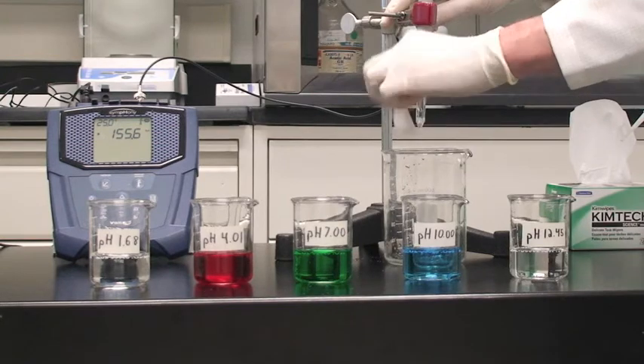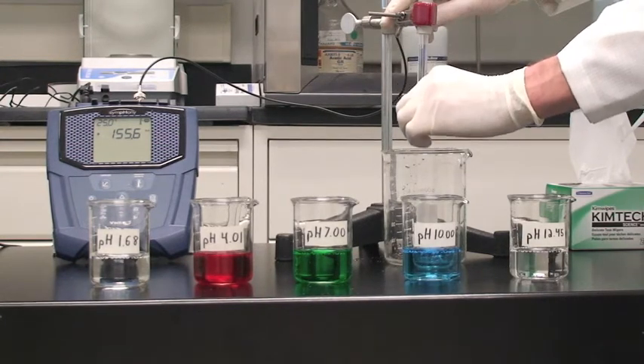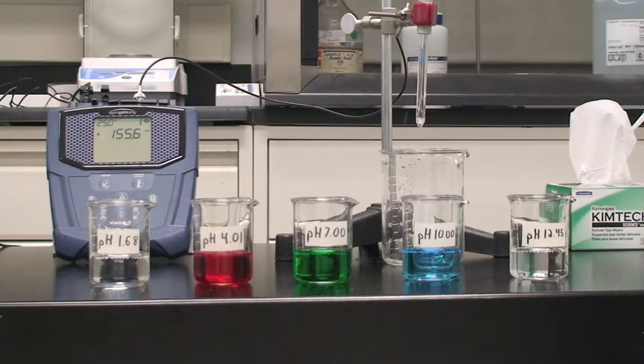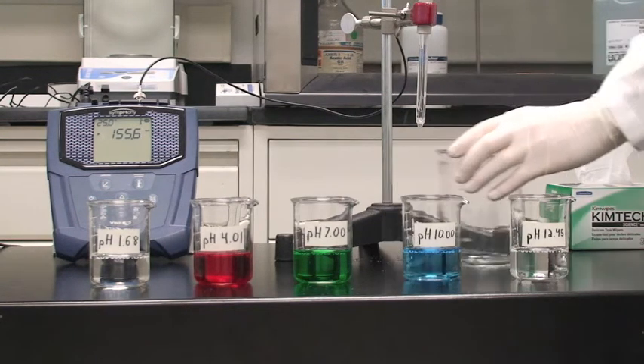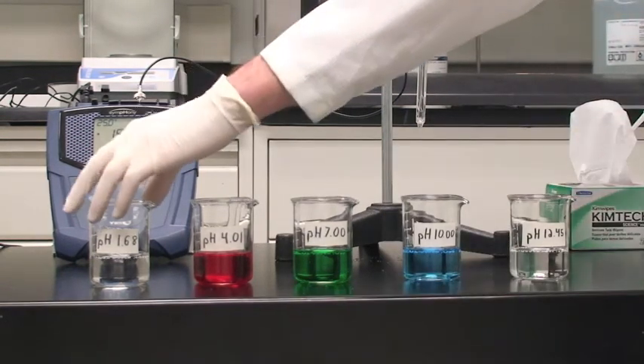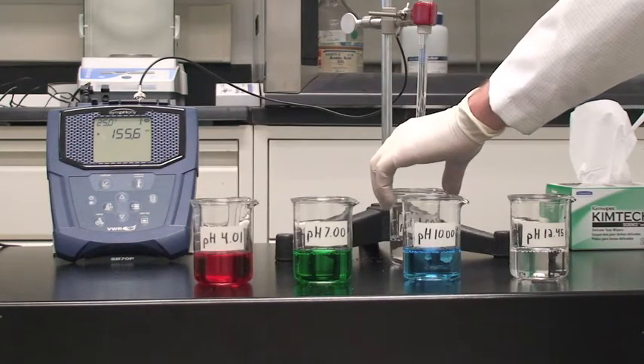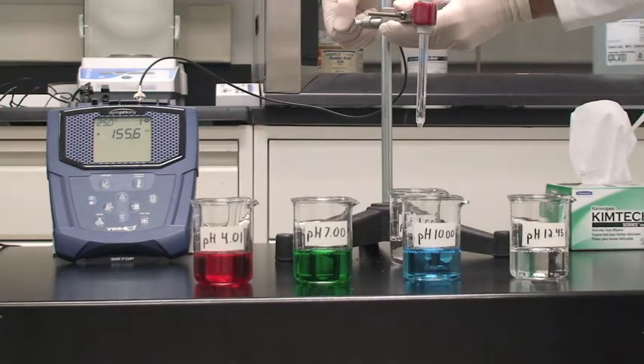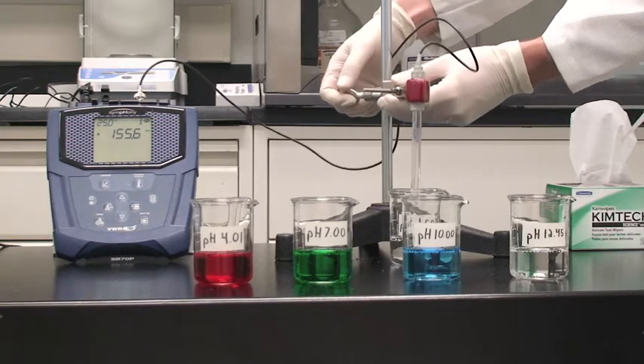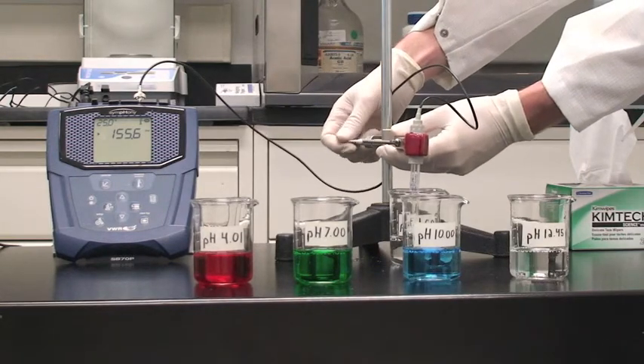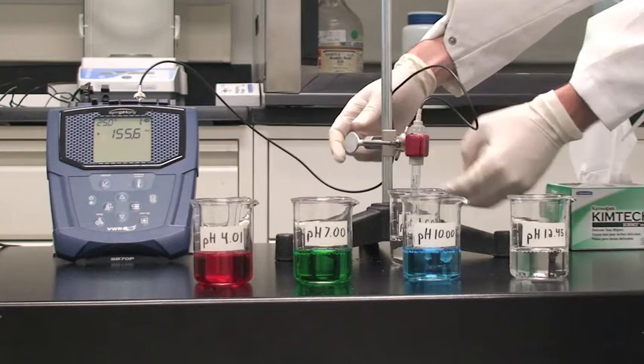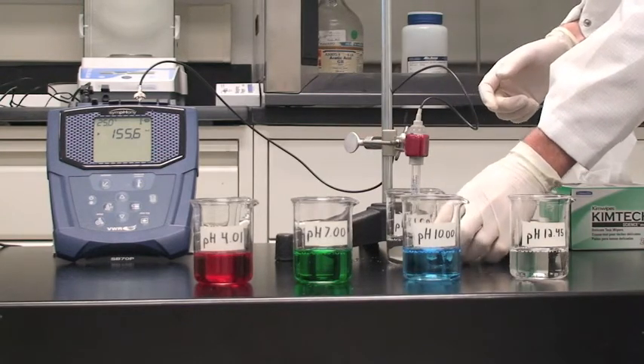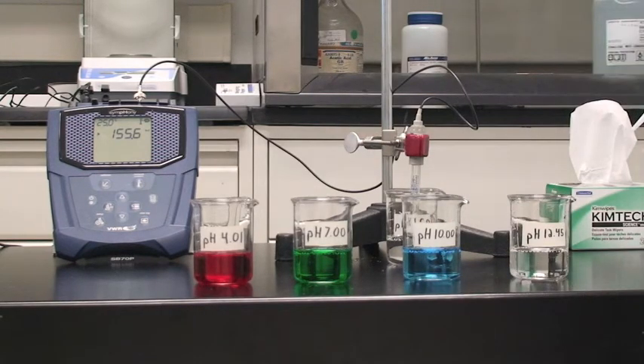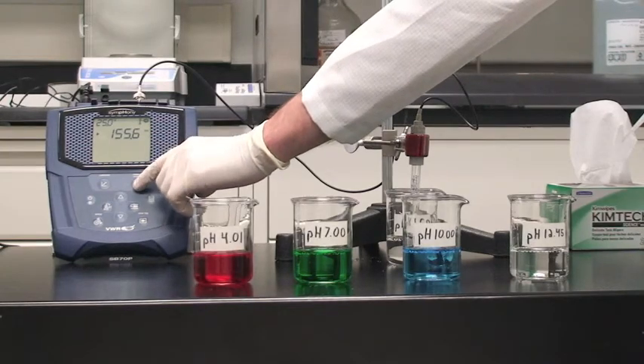The calibration curve will be generated by using 5 pH buffer solutions with a known pH of 1.68, 4.01, 7.00, 10.00, and 12.45. When immersing the probe into the buffer solution, be careful not to let the glass bulb hit the bottom of the beaker and crack. Once the probe is immersed, we set the pH meter to measure cell potential and use this voltage to calculate the proton activity.